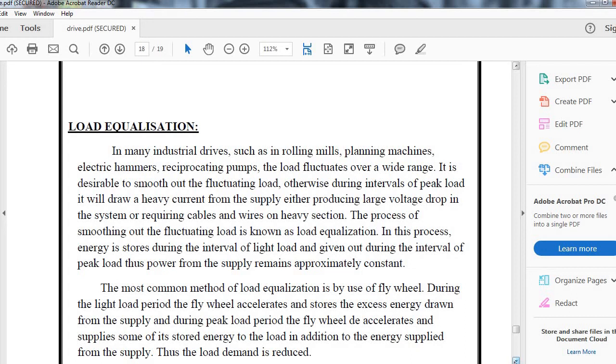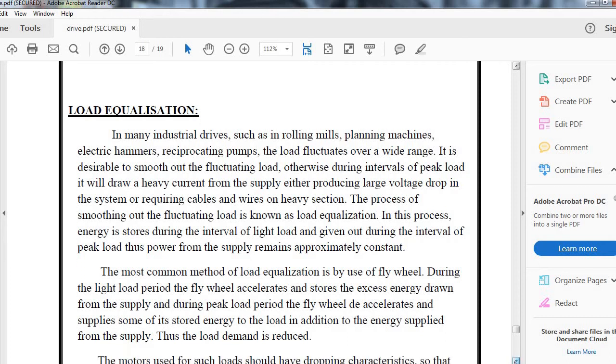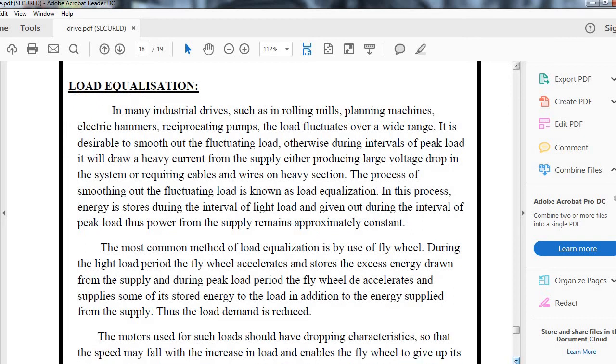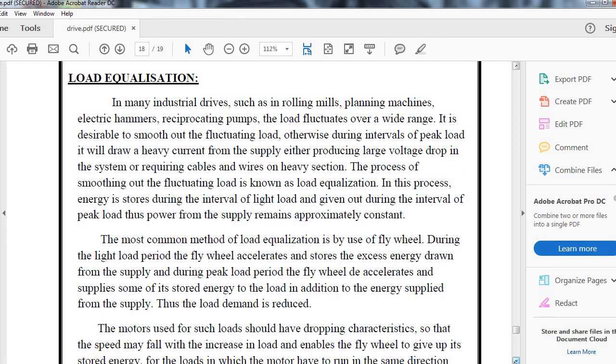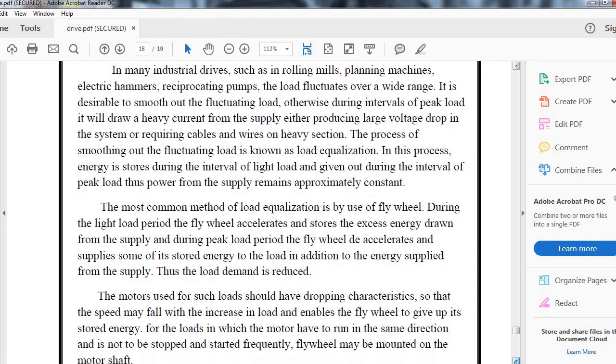In this process, energy is stored during light loads and released during peak load intervals, thus the power from the supply remains approximately constant. The most common method of load equalization is by use of flywheels. During light load periods, the flywheel accelerates and stores excess energy. During peak load, the flywheel decelerates, supplying some of its stored energy to the load in addition to the energy from the supply, thus reducing peak load demand.